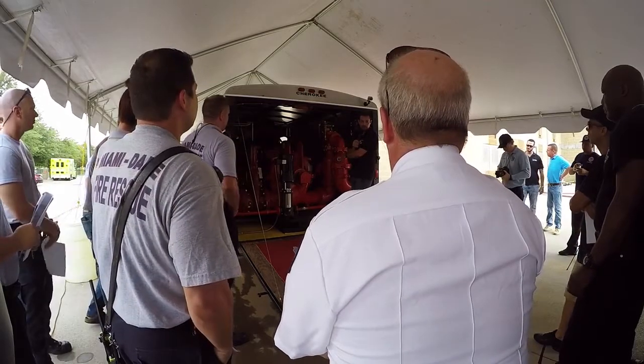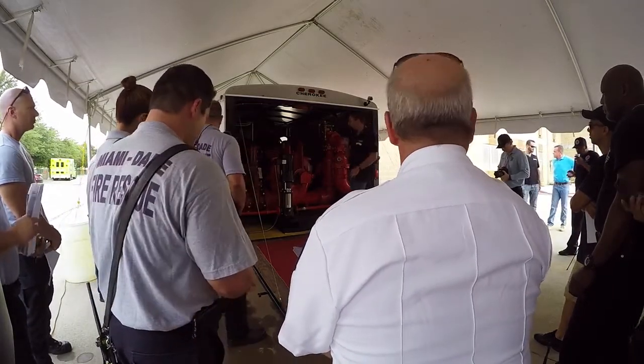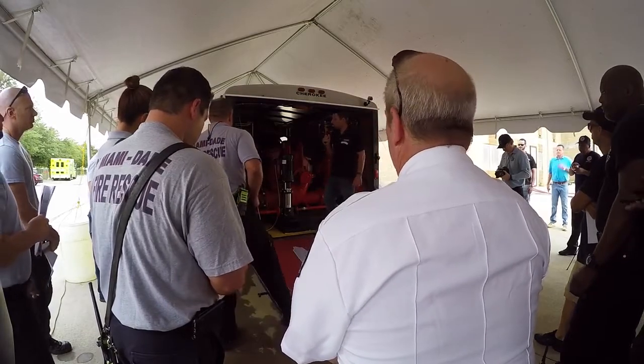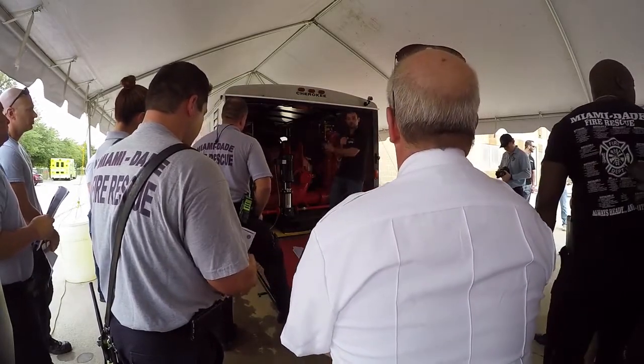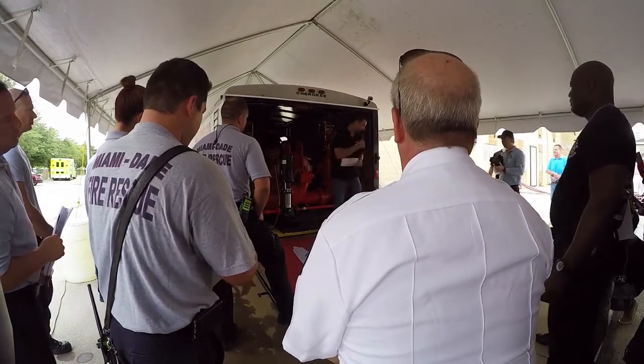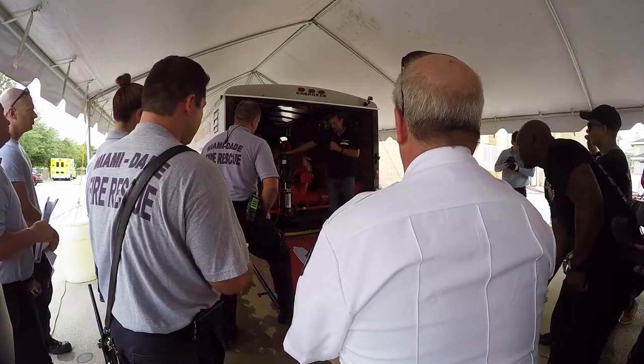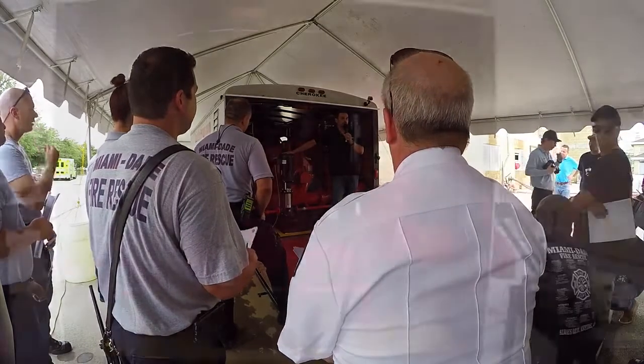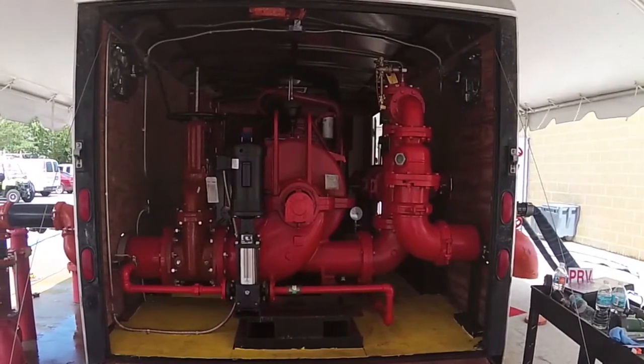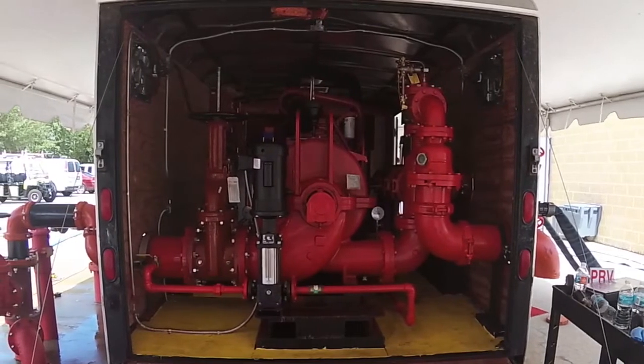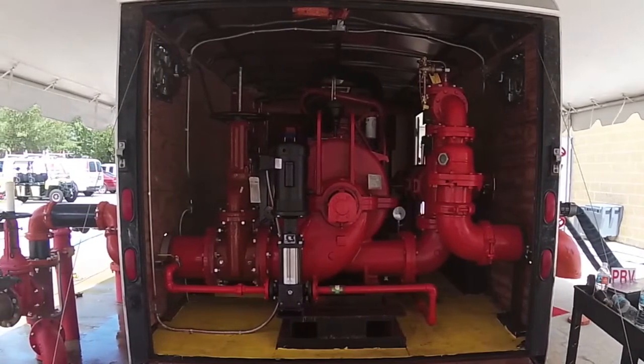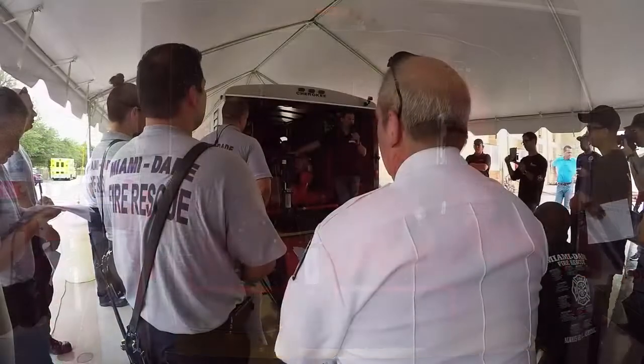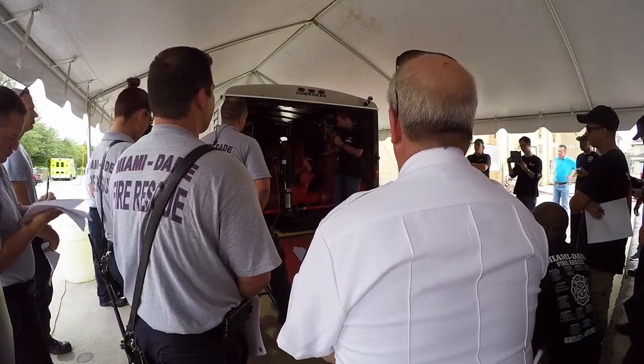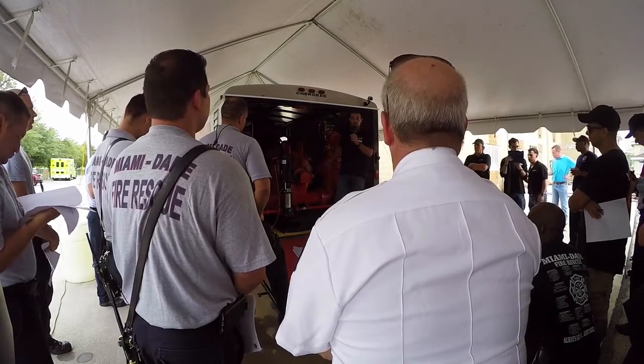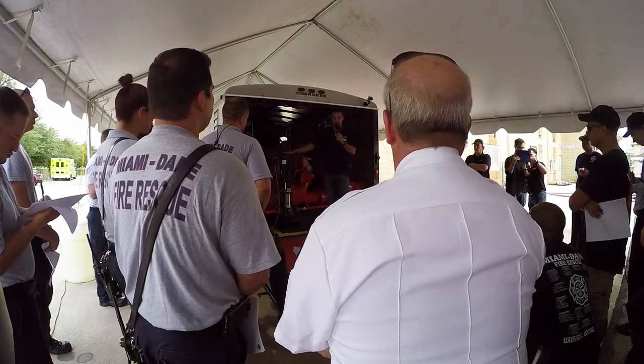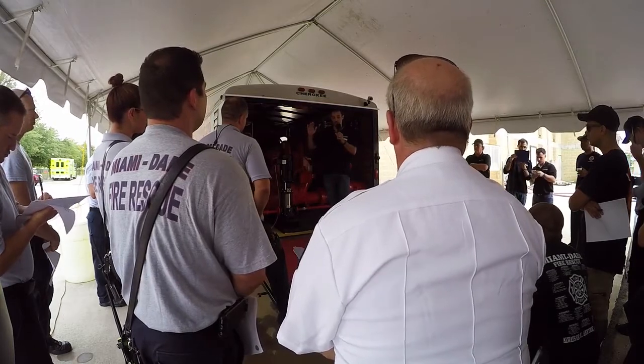Depending on the building and the circumstance, it gets pretty high, okay? To keep the pressure up in the building or to drain and fill, we don't use the fire pump, we use what's called a jockey pump. There's a small pump right here. When we drain, when we fill, when it loses pressure, this will keep the pressure in the building up, okay? The way the sprinkler system works is it all works on pressure. So a sprinkler head goes off or someone opens a valve, we start losing pressure on the discharge side of the pump. Pressure drops, jockey pump's going to start just to keep the pressure up, okay?